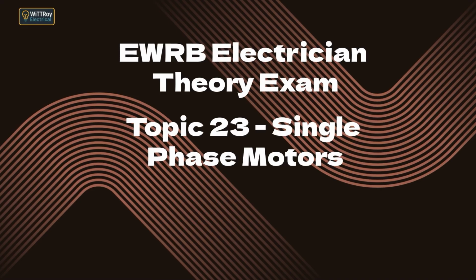Topic B. Explain how phase splitting can be used to provide starting torque in a single-phase motor. To create starting torque, we need a rotating magnetic field. Single-phase motors achieve this using phase splitting. Phase splitting means adding a second winding, the start winding, that is intentionally made out of phase with the main winding. This can be done by resistance, split-phase motor, a capacitor, capacitor start, capacitor run, PSC, etc.